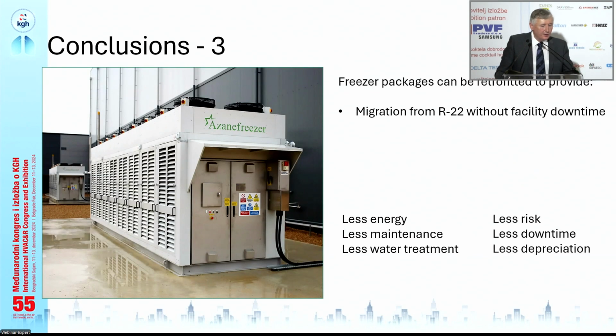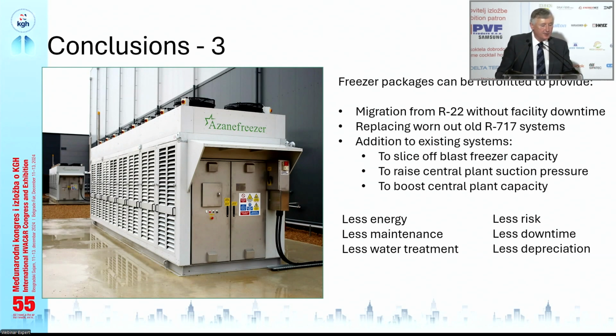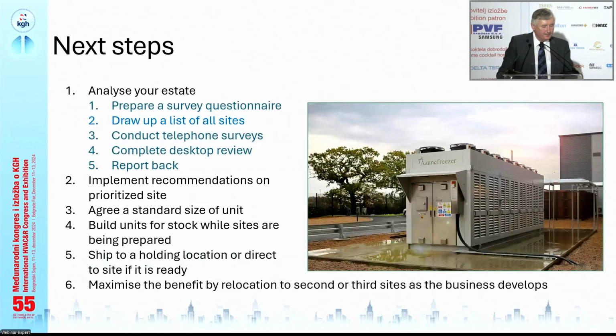So some final conclusions. We can retrofit the package to migrate from R22 without any facility downtime, to replace old worn-out ammonia systems, to add to existing systems, either taking off some capacity, as I mentioned, raising the central plant pressure, or boosting the central plant capacity. So how would you do this? Just final slide, some next steps.